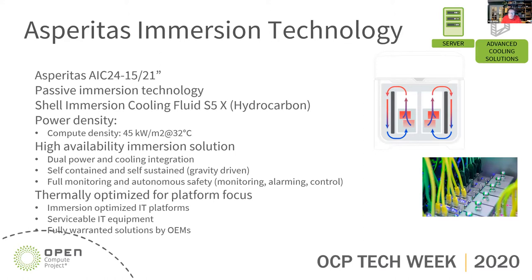Before I get into the details around platforms, I want to give a brief frame of reference on where Asperitas is engaged. Asperitas is a liquid technology vendor working with single-phase immersion, and our circulation mechanism is based on natural convection. Our system is completely passive in nature, and the driving force behind the liquid flow is heat.